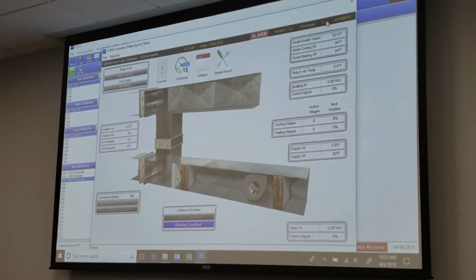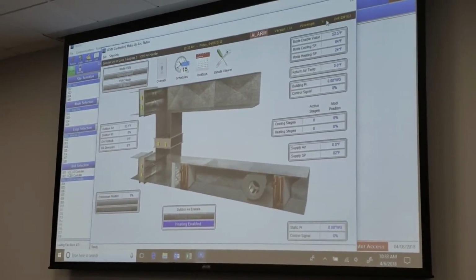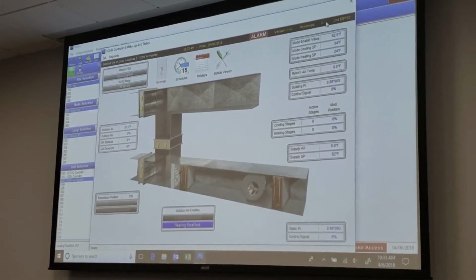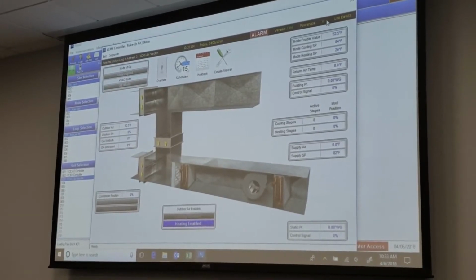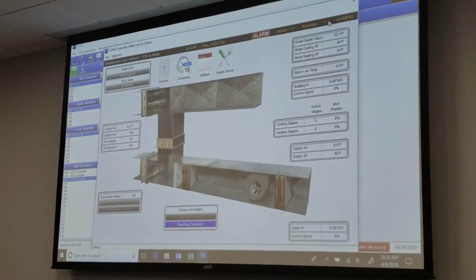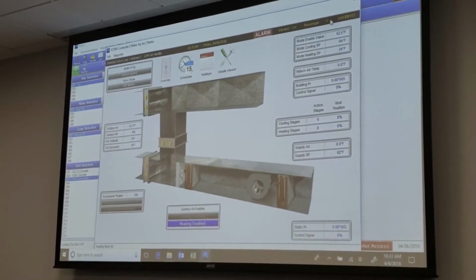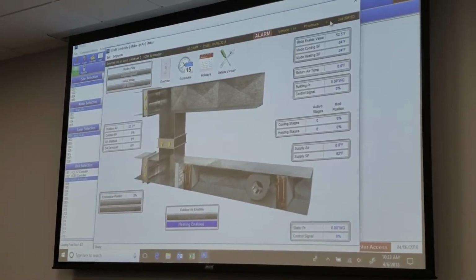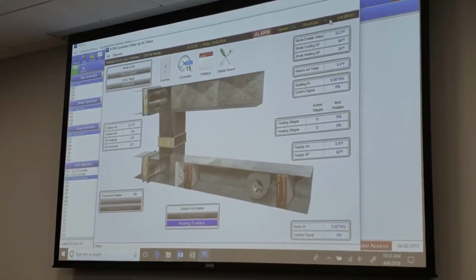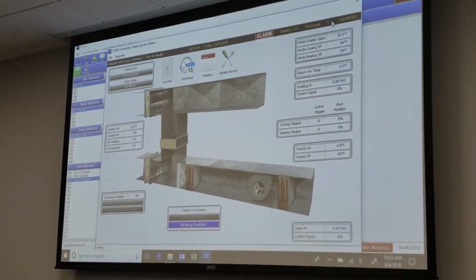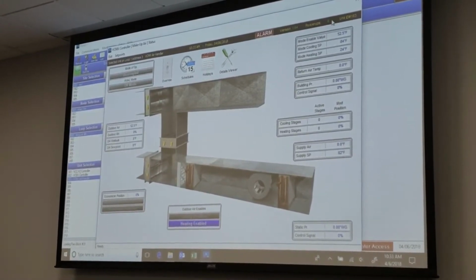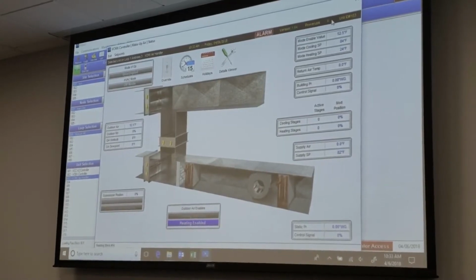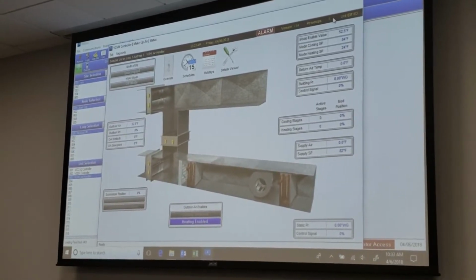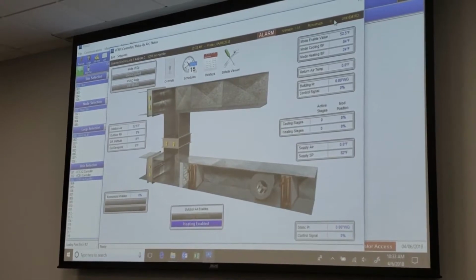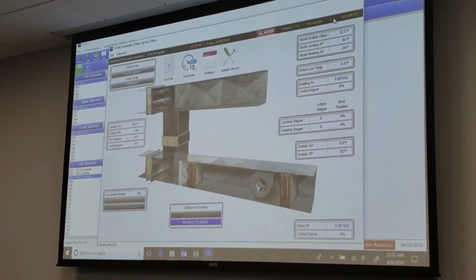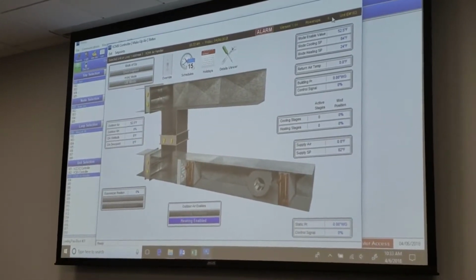Had a job site at Dow where they had 13 labs. I was actually monitoring all 13. Looked at all of my units, and one unit was shut down. They kept saying, no, you got a problem with your unit, Renee. And I looked at all the power up counts on all of them, and there were about 2 or 3 doing maintenance or whatever, shutting down for whatever reason. This other one was sitting at like 1,300 power up counts. Said, hey guys, y'all got something going on here, man.